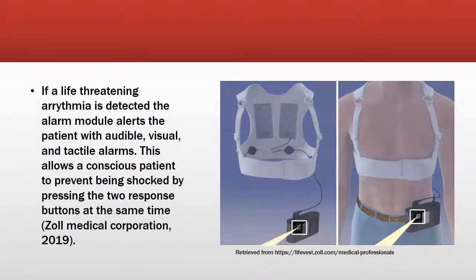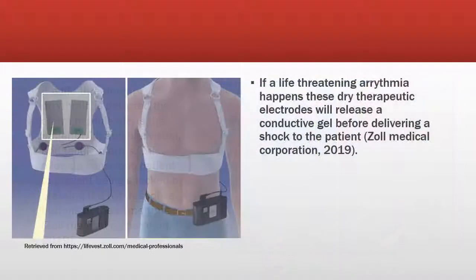If a life-threatening arrhythmia is detected, the alarm module alerts the patient with audible, visual, and tactile alarms. This allows a conscious patient to prevent being shocked by pressing the two response buttons at the same time. If a life-threatening arrhythmia happens, these dry therapeutic electrodes, which you can see here to the left on this picture, will release a conductive gel before they deliver a shock to the patient. The Zoll LifeVest uses a blue gel.